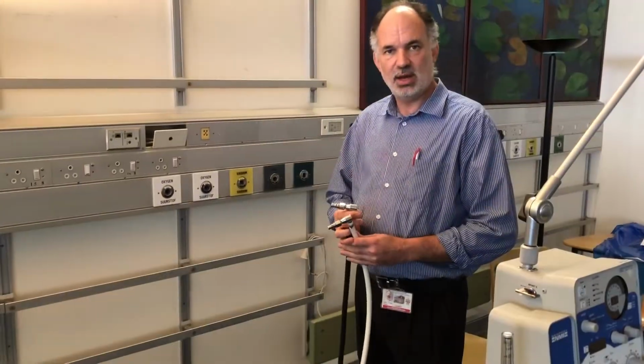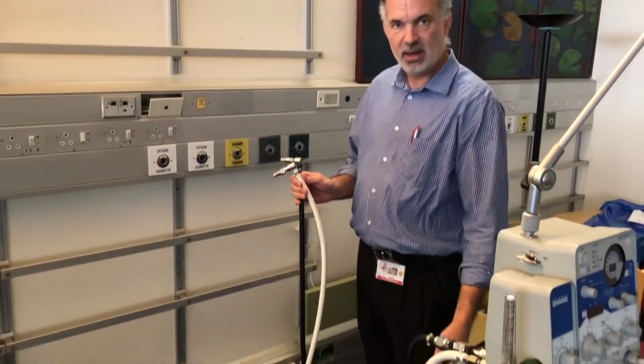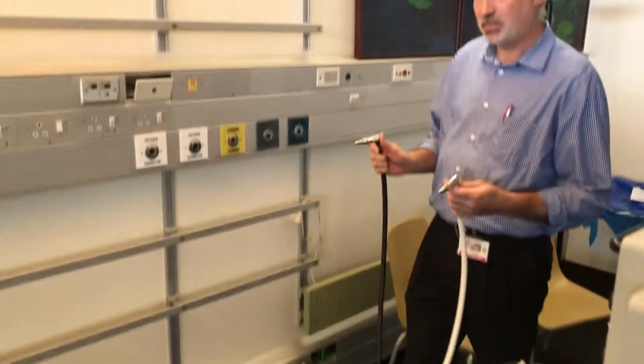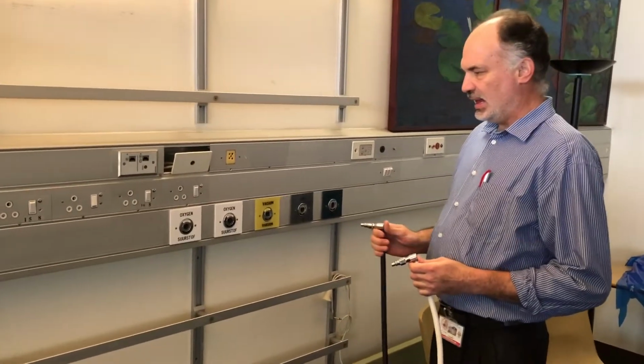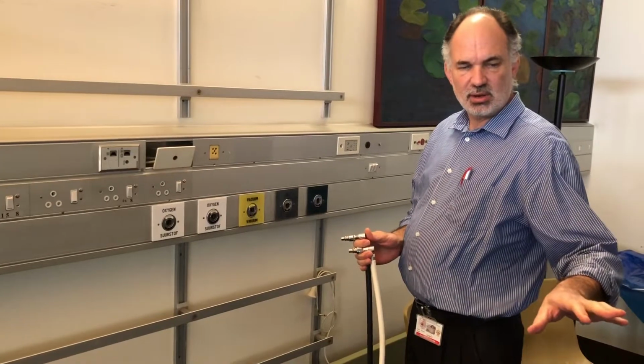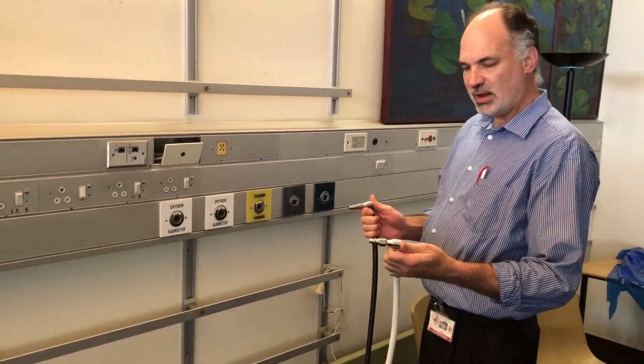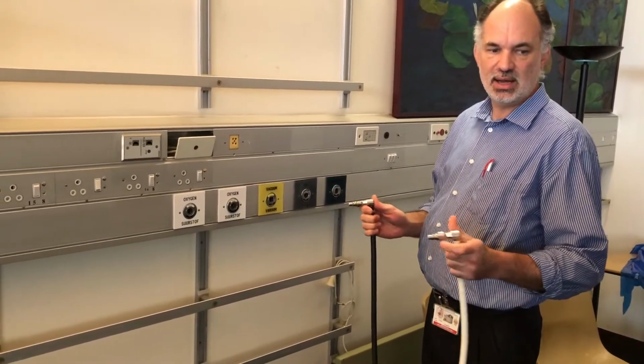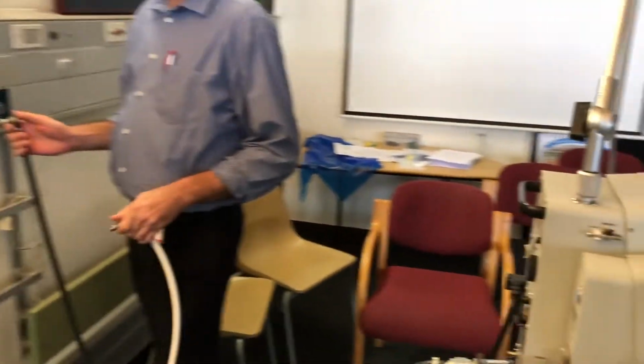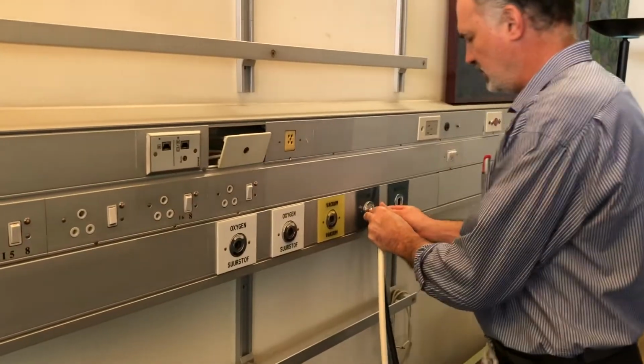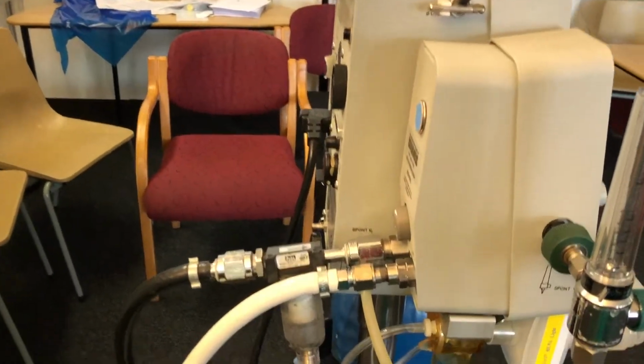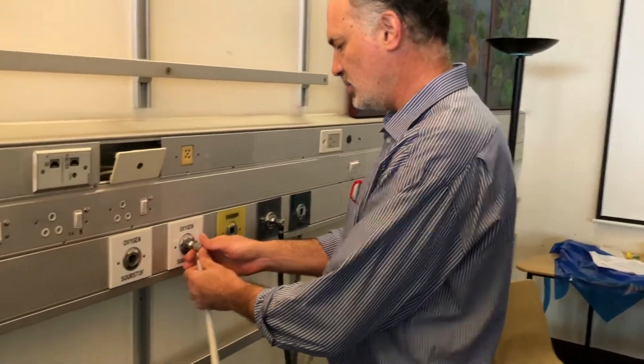Right, so we're going to go through connecting the ventilator up. I'll just plug the electrical supply into the wall, and we're going to connect up the gas connections. And just to make you all aware, because the machine's got an old style blender in it, if we don't have both of these plugged in correctly, the machine's going to make a loud squeak from the blender. So I'm just going to plug the air in first. And you can hear now, that's the blender making that noise. And the reason the blender is making the noise is because there's no oxygen connected. So I'm going to go and connect the oxygen.